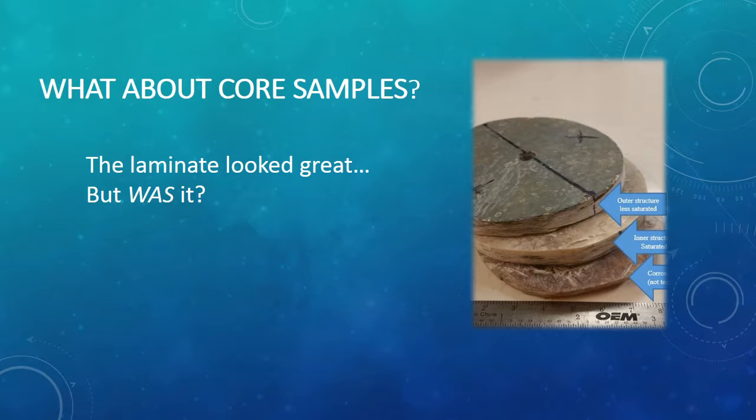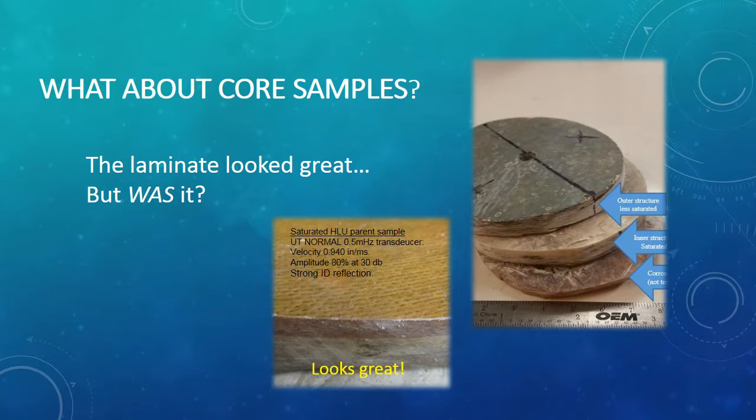The following is an example of how a core sample confirmed MFI in the field. We tested an 18-inch diameter by 1-inch thick stock line and found full permeation to within almost 3/16 of an inch to the outside surface, or 0.188, even though the pipe wall was around 1 inch total thickness. We took a core and it looked great visually. It was 1 inch thick. The inner surface still retained the original gloss, and the veil was embedded in the original molded surface.